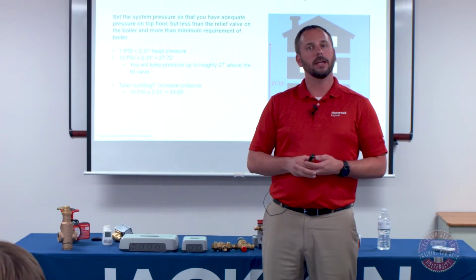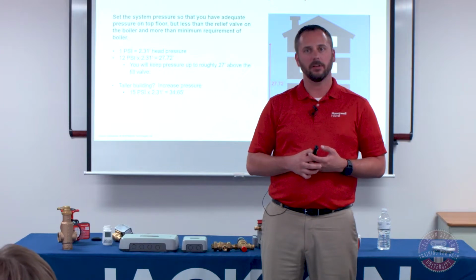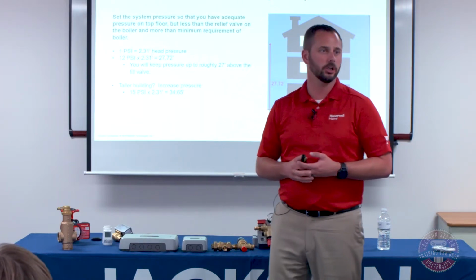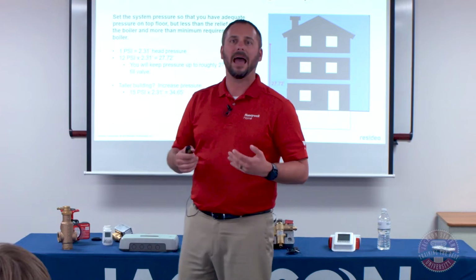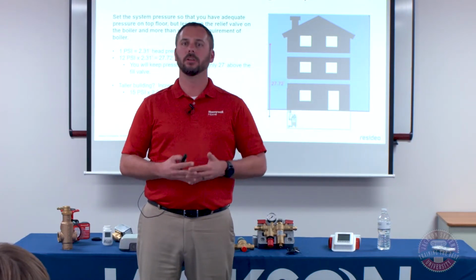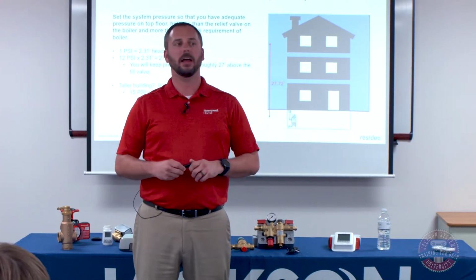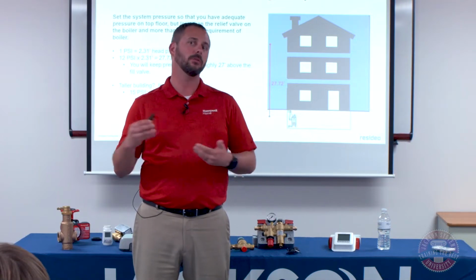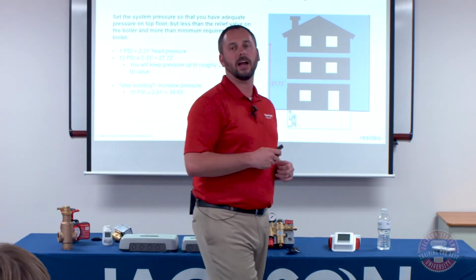So what you need to do is keep an eye on the relief valve setting on the boiler. Always give yourself a little bit of cushion. A lot of boilers do have the capacity to go with a higher pressure relief valve. So you may have to adjust that relief valve from a 30-pound to a 50-pound. But always check the manufacturer's ratings on your boiler.